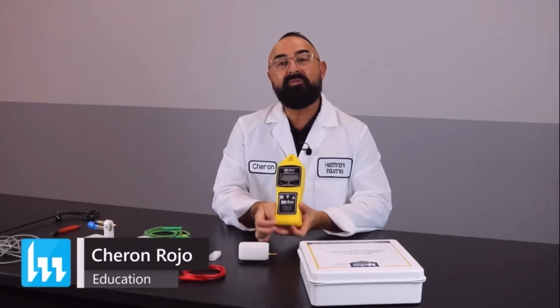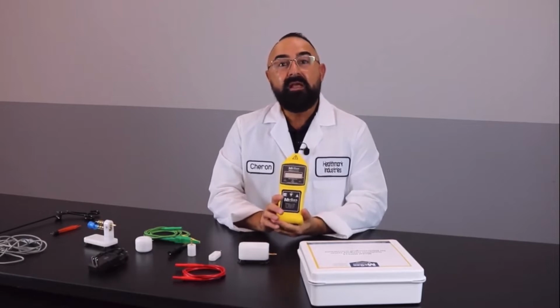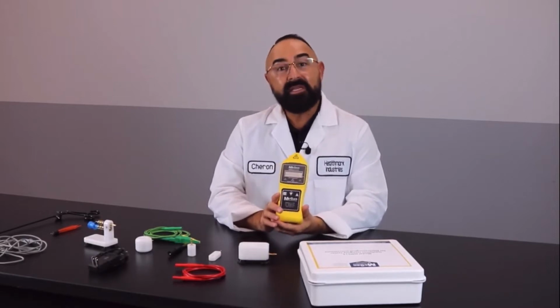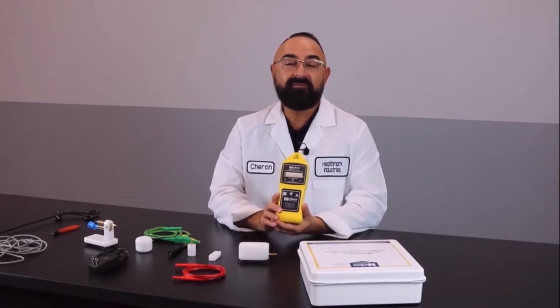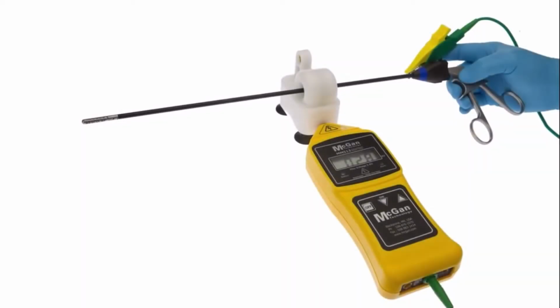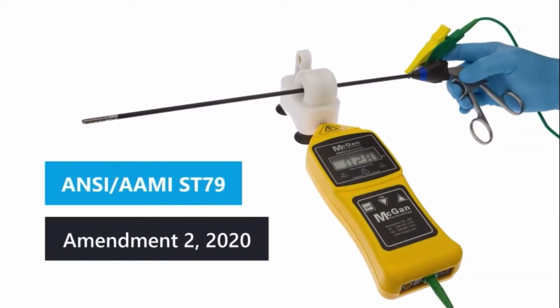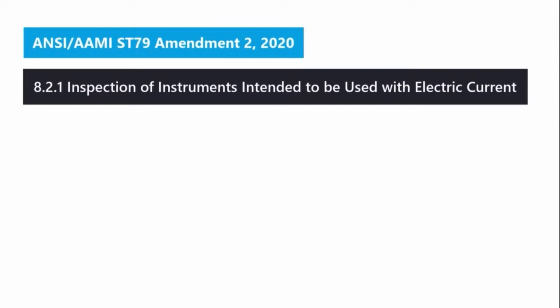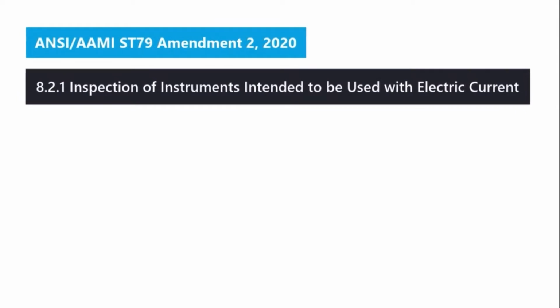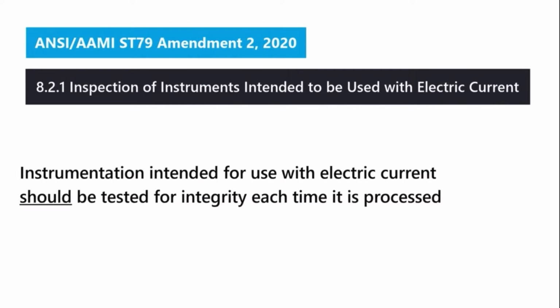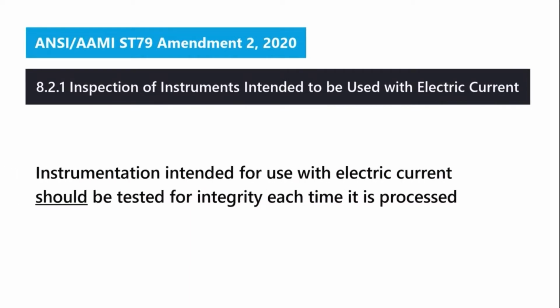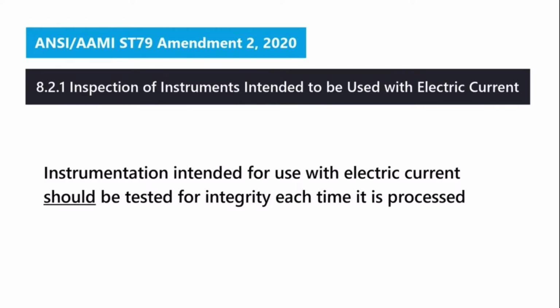Today we're going to go over the McGann insulation tester that actually tests for damage on your insulated instrumentation. Our product solution, the McGann insulation tester, can help you meet the standards and recommendations for the new ANSI/AAMI ST79 Amendment 2 2020. Under the new Amendment 2, 8.2.1, under inspection of instruments intended to be used with electric current, it states that instrumentation intended for use with electric current should be tested for integrity each time it is processed.